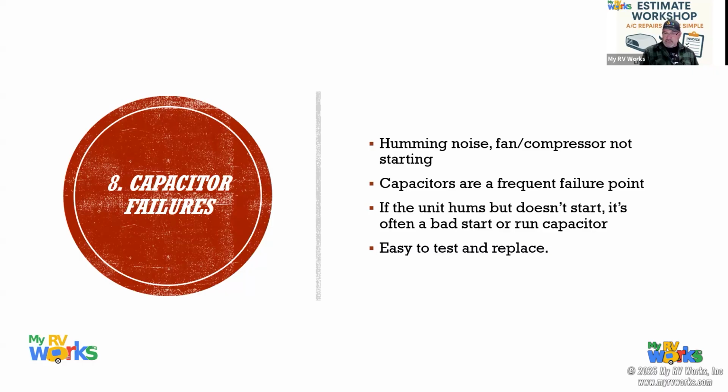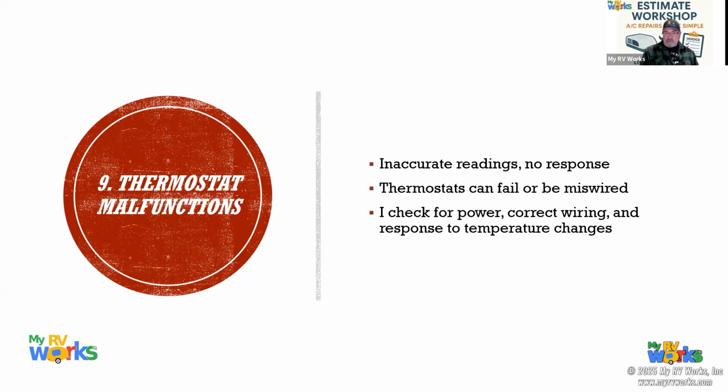Number nine, capacitor failures. They're very easy to test and replace, but it's a very common fault with a capacitor, especially in the air conditioners down south where it's working really, really hard. These capacitors get really, really hot, and they just burn out. They fail.